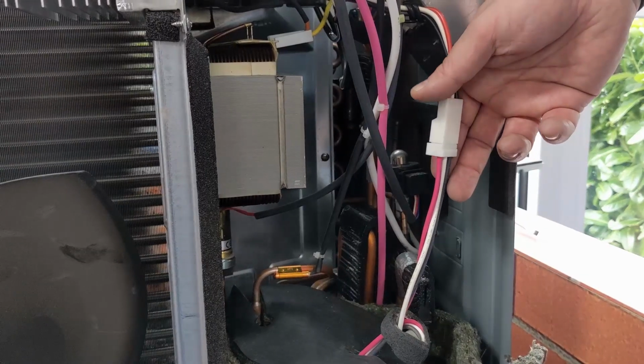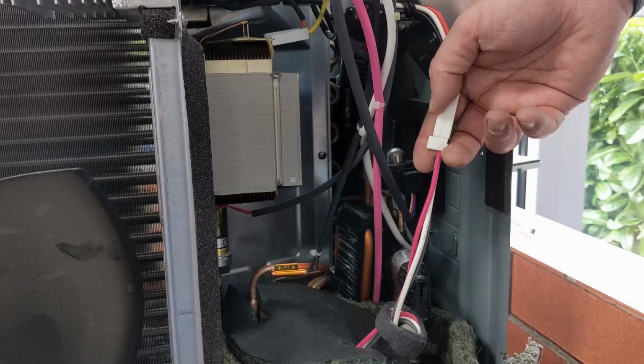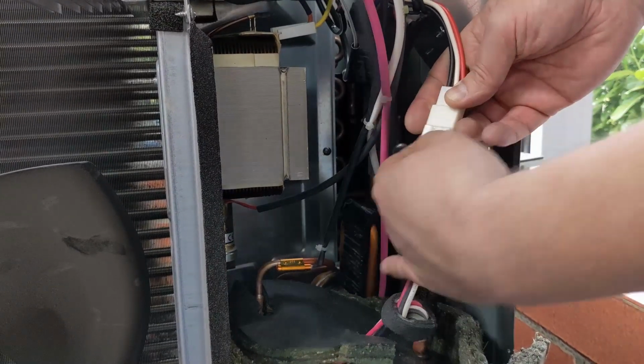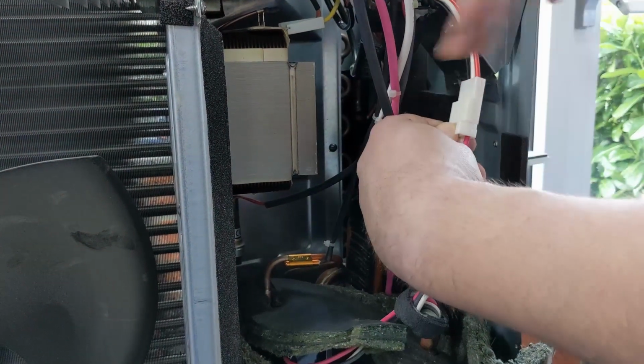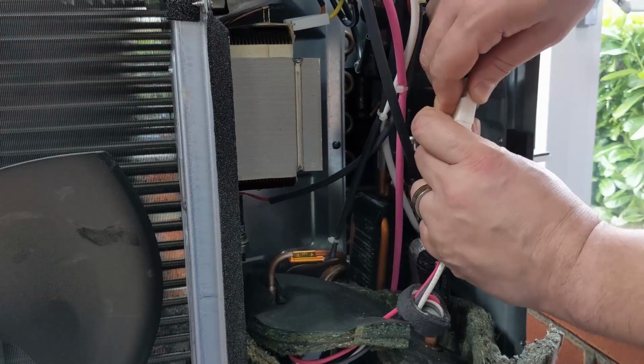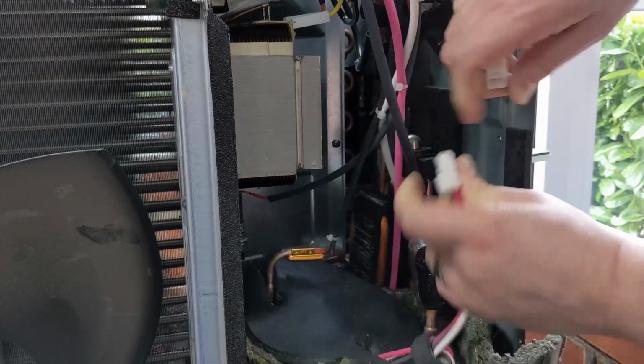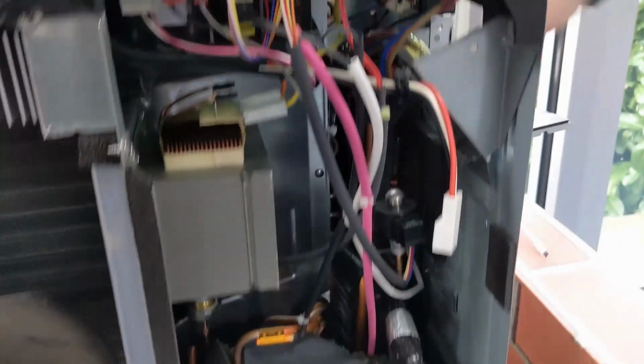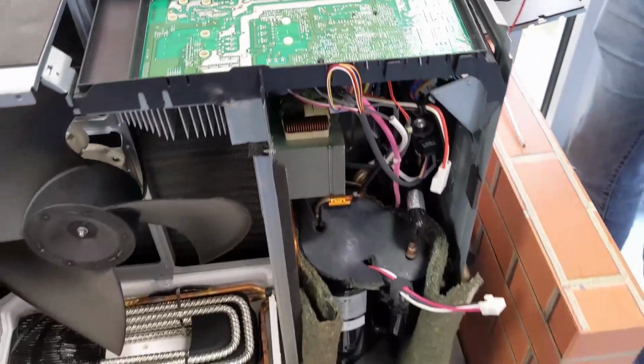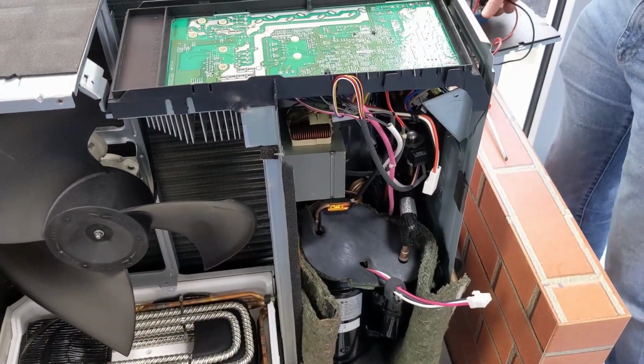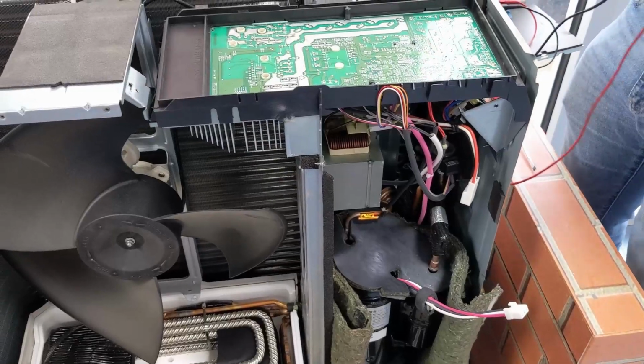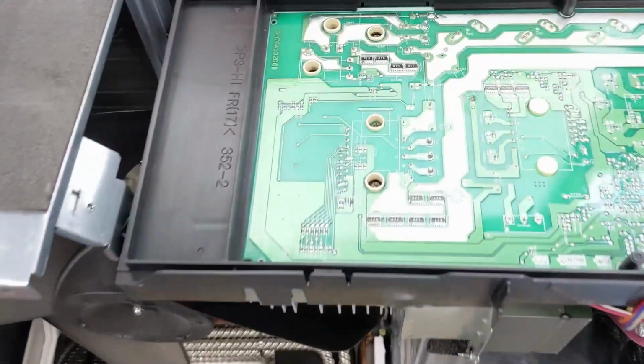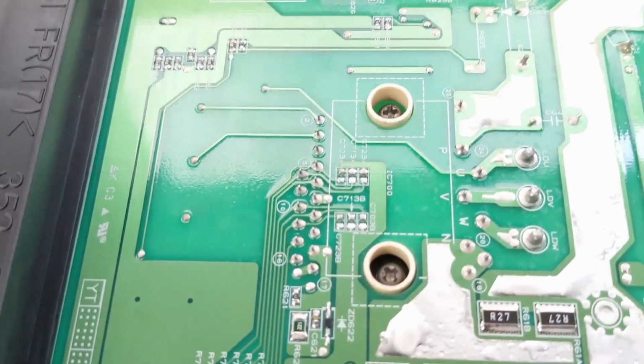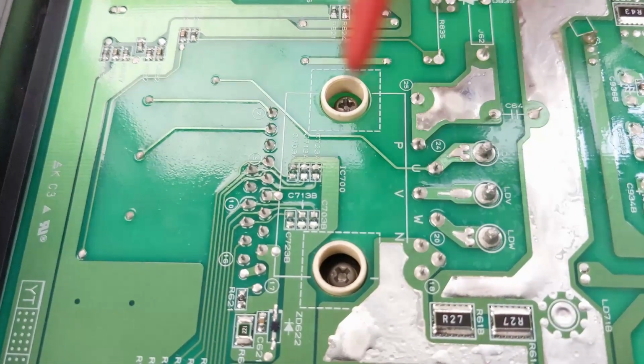So we're doing an inverter test, obviously on the basis that the capacitors have all discharged, so give it a good 5 minutes. We can disconnect the inverter from the actual compressor itself. You then put power to the unit. Fan will come into life, so bear that in mind. And then what we do is we simply test across between those connections on the back of the board.